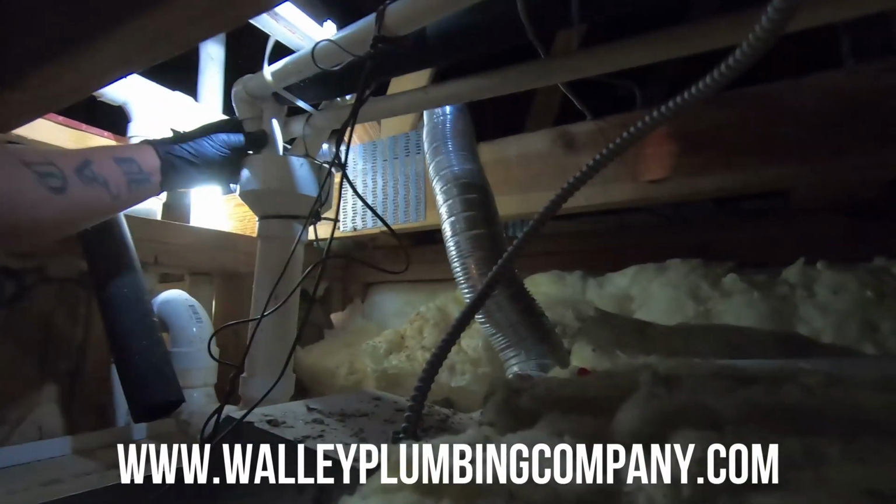So the first plumbing problem we're going to is, the description I have is water coming out of the ceiling. That's one that can't wait. I'd love to be at the shop doing a video on how to do whatever, but we're going to show you firsthand how to get somebody out of a plumbing bind here. Water coming out of the ceiling. So this is a condensate drain that's full of sludge. It looks like we have a condensate backup from this hub drain in the sewer.